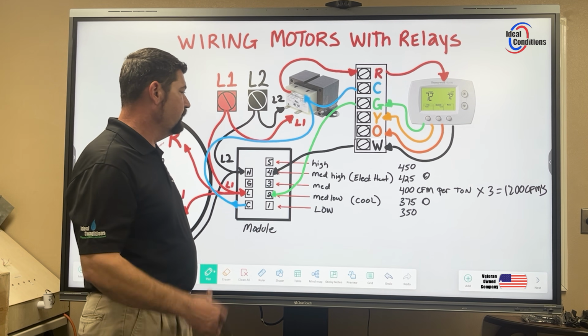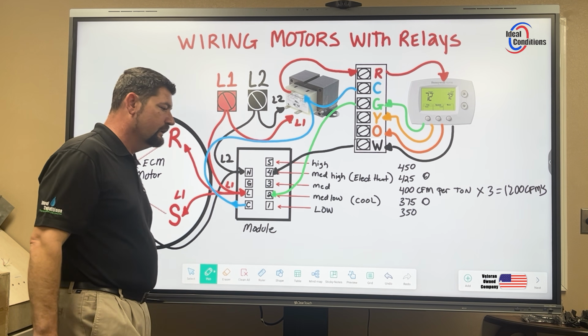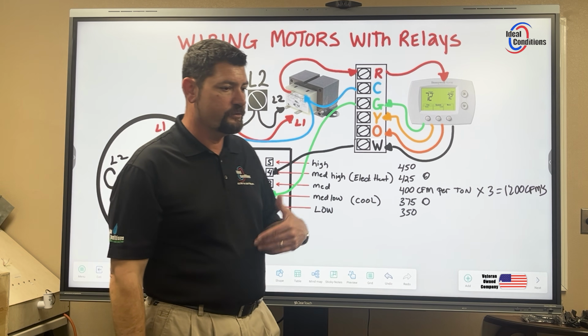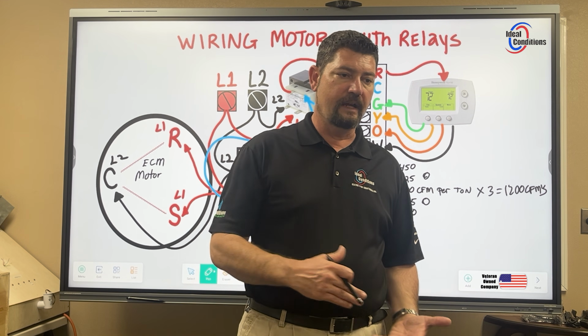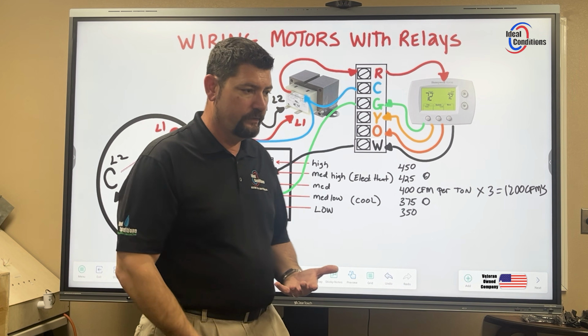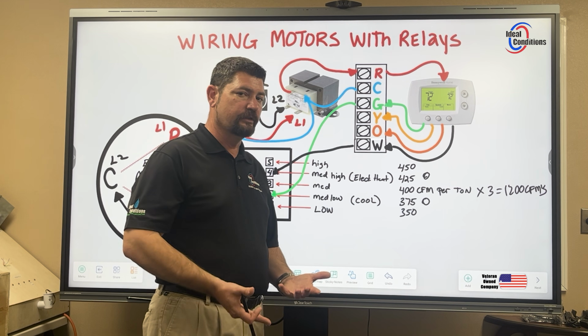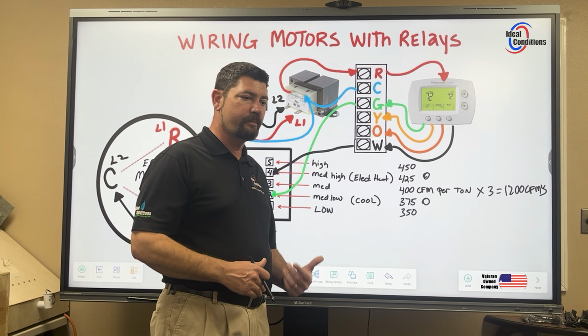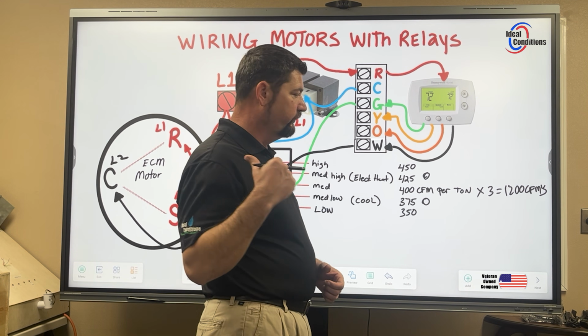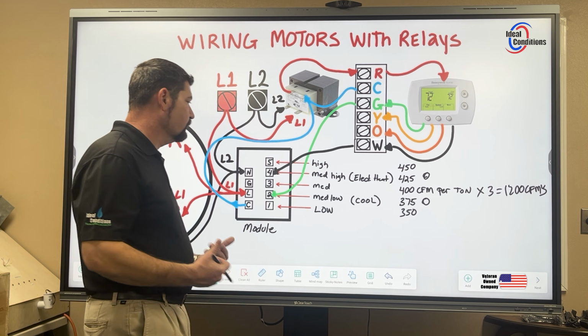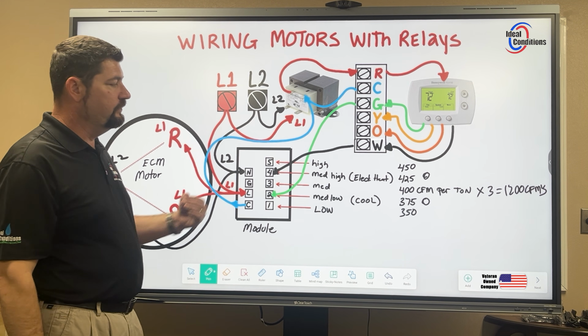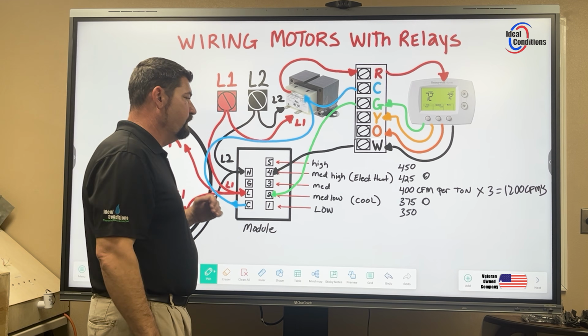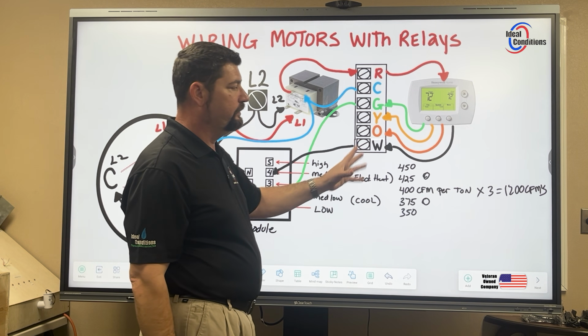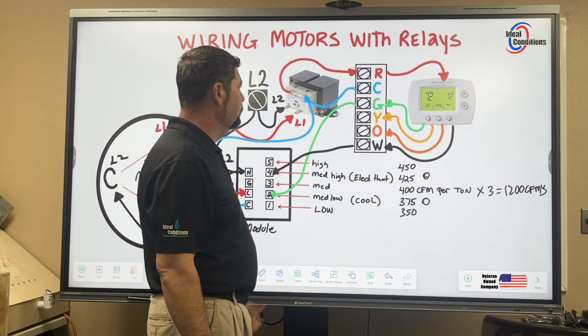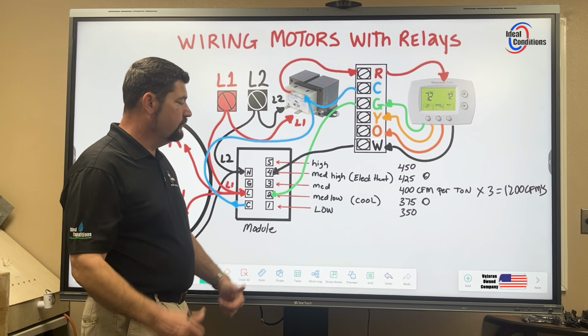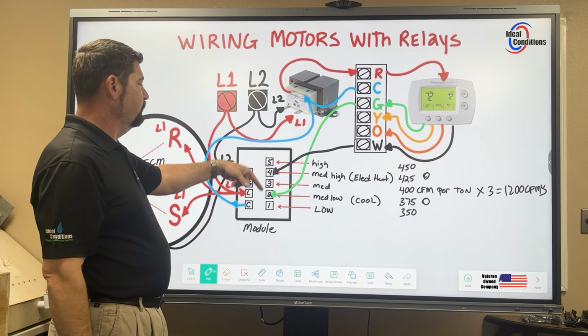All right, CFMs is your air handler, your BTUs is an output of the air handler, but it's as a result of what is it? Is it an output of the heat strips, and then that's going to change with how much airflow is going across it? Is it an output off your evaporator coil because we're transferring heat from outside to inside? Those BTUs are always changing. So if our BTUs increase, we need to make sure that we can distribute that properly with the proper CFMs. And that's why these heat strips or Y2s will govern the next speed.